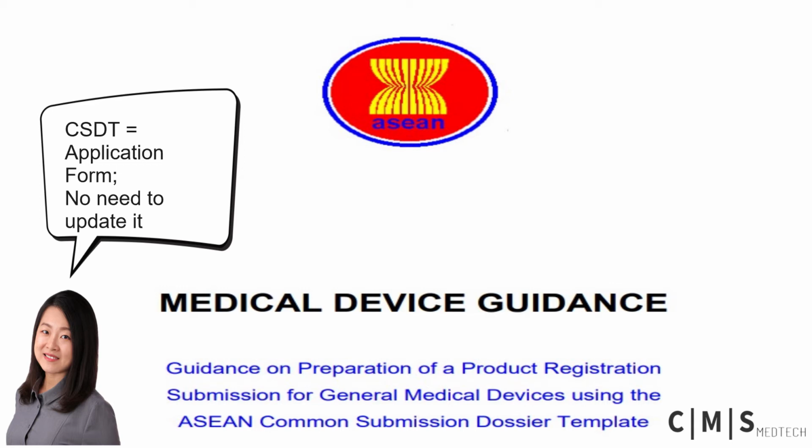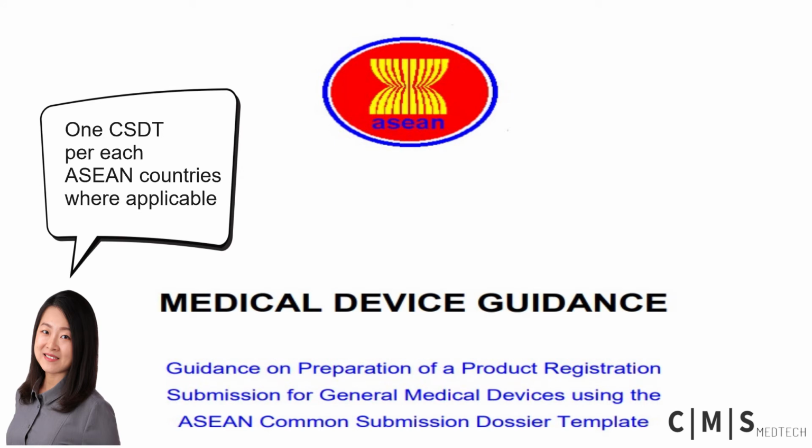Also, the CSDT formats among ASEAN countries are not harmonized yet, unlike the EU technical file. This means you need to submit one set of CSDT to, say, a country like Singapore to gain regulatory approval, but you would need to submit a different CSDT format to another country, say Vietnam. Hence, it could somewhat be deduced that the purpose of the CSDT is only to align the terminology of the requirements among ASEAN countries. Regardless, it is always beneficial to learn the format of the CSDT in general, as the requirements among ASEAN are still similar, although not 100% identical.